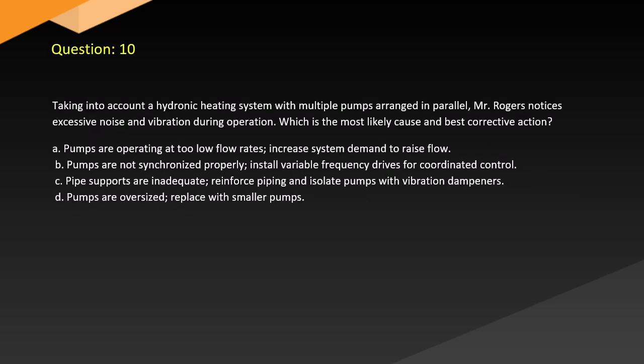Question 10. Taking into account a hydronic heating system with multiple pumps arranged in parallel, Mr. Rogers notices excessive noise and vibration during operation. Which is the most likely cause and best corrective action? A. Pumps are operating at too low flow rates. Increase system demand to raise flow. B. Pumps are not synchronized properly. Install variable frequency drives for coordinated control. C. Pipe supports are inadequate. Reinforce piping and isolate pumps with vibration dampeners. D. Pumps are oversized. Replace with smaller pumps.